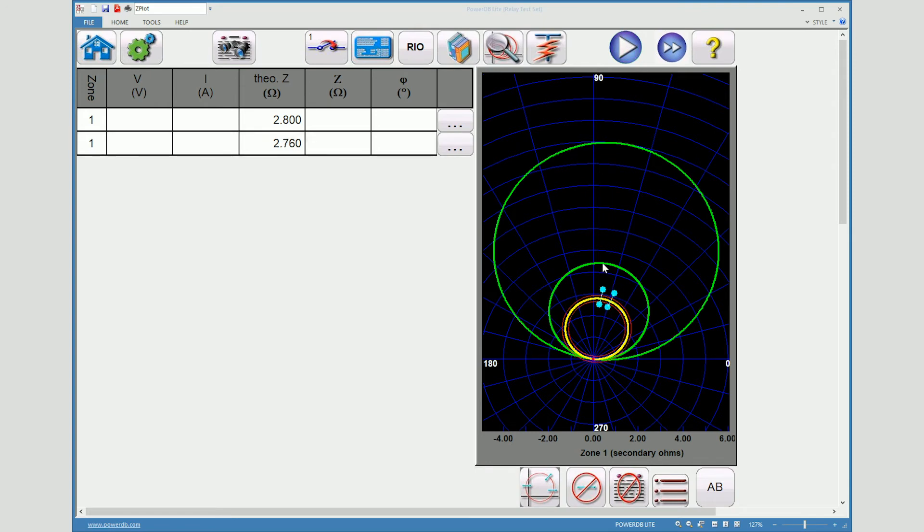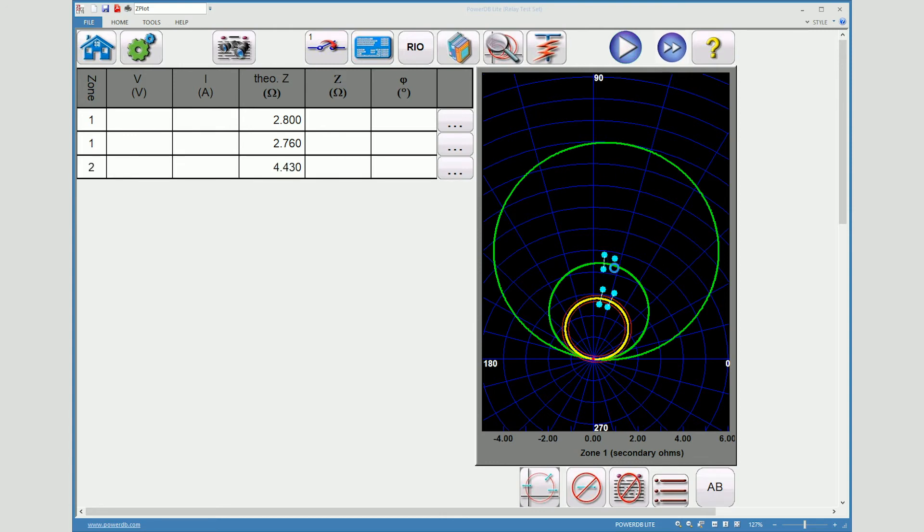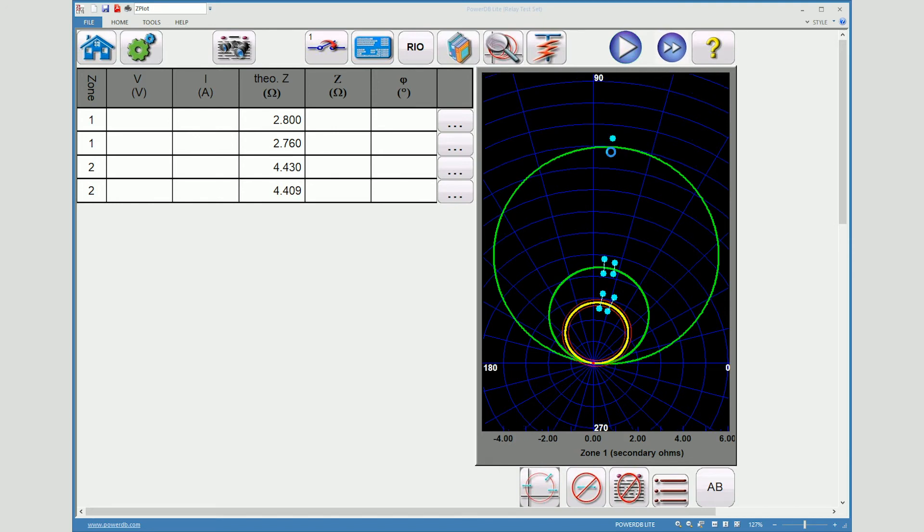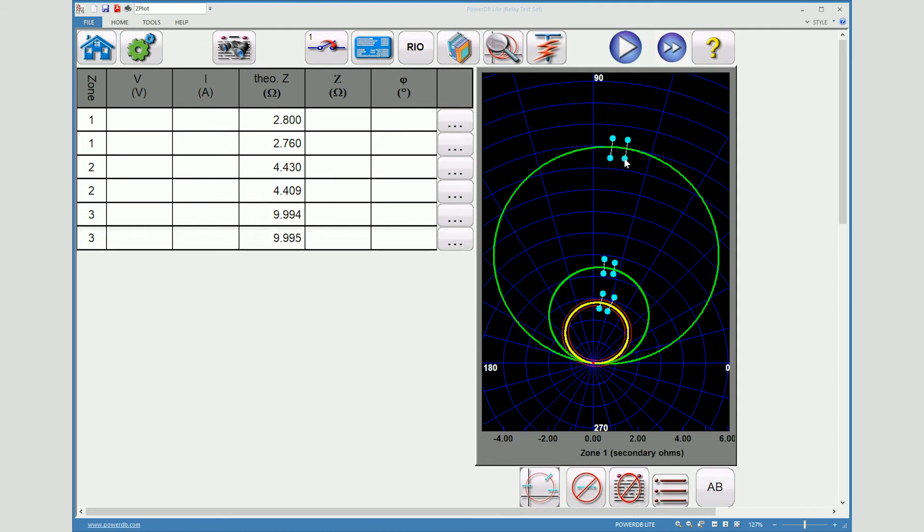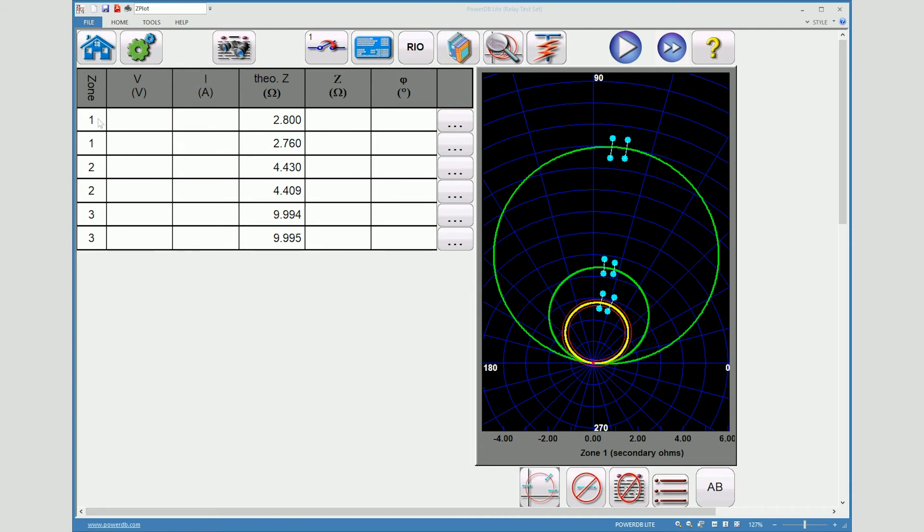Now that we can come in for zone two, we can also see that zone two is here with the green circle. We can click a couple points outside of that as well. And then also we want to test in the zone three area, preferably pretty close to our maximum torque, which is the Z1 Ang. So now that I have two points inside of zone one, two points into zone two and zone three. Now you notice that these have populated on our table next to us. And then they signify what zones they were actually plotted in. They were in zone one and zone two and zone three. So I have six tests here.